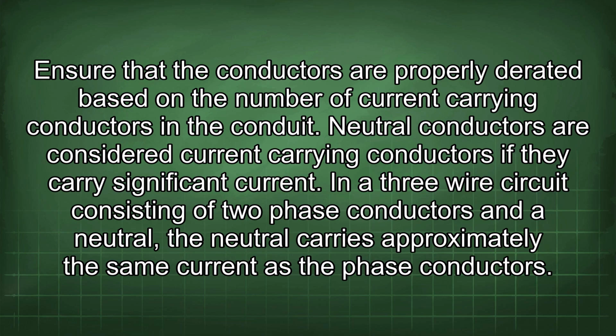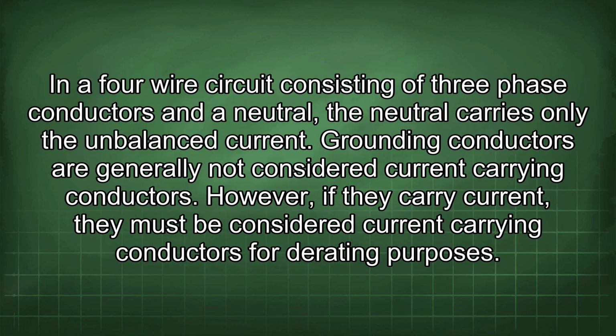In a three-wire circuit consisting of two phase conductors and a neutral, the neutral carries approximately the same current as the phase conductors. In a four-wire circuit consisting of three phase conductors and a neutral, the neutral carries only the unbalanced current. Grounding conductors are generally not considered current-carrying conductors. However, if they carry current, they must be considered current-carrying conductors for derating purposes.